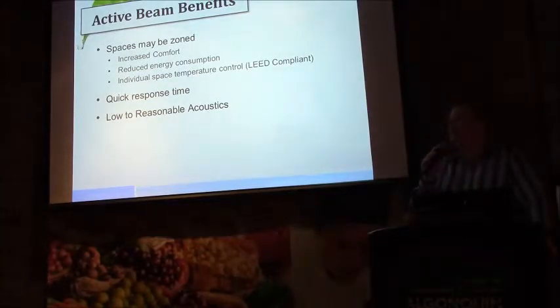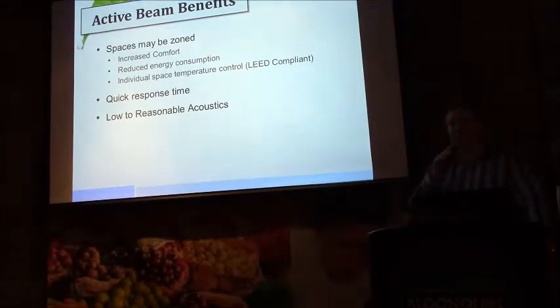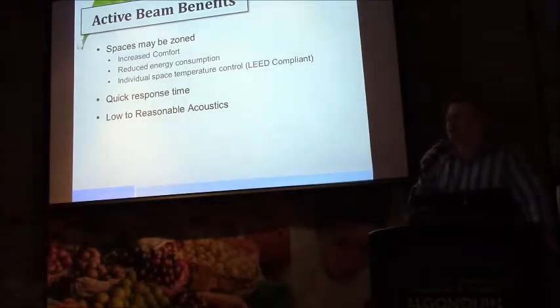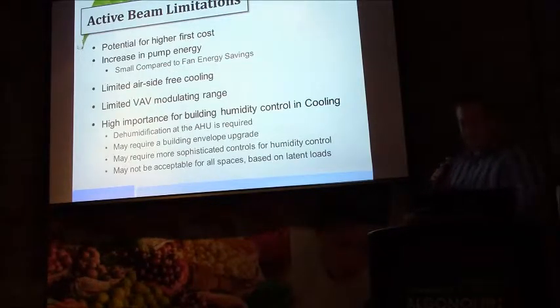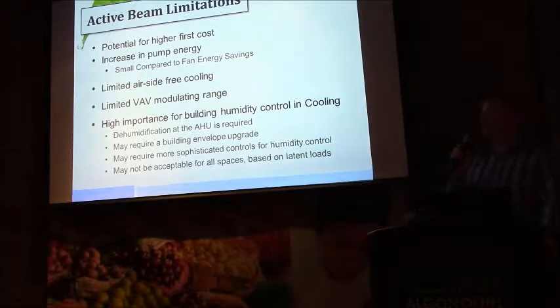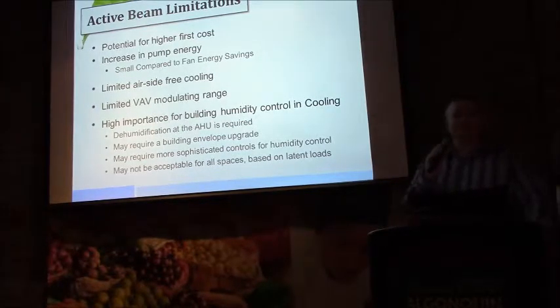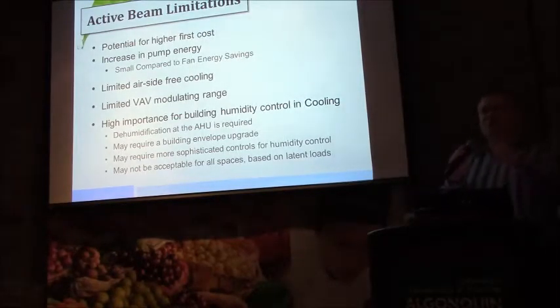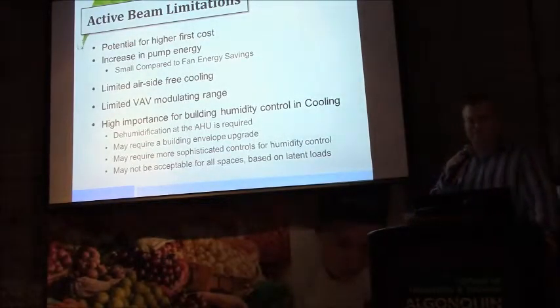is controlled comfortably and deals with all of the elements that have been defined in the discussion that typically is held with the architect, and conceivably even better yet, the owner. Because if you understand what it is that is expected of the space relative to churn, relative to acoustics, a more tailored solution can be brought to bear. And so that obviously has the potential for higher first costs. But those decisions were made knowingly. It wasn't a drop-in solution to deliver X number of BTUs. All of the elements were a weighted basket to provide the deliverable to the end user.